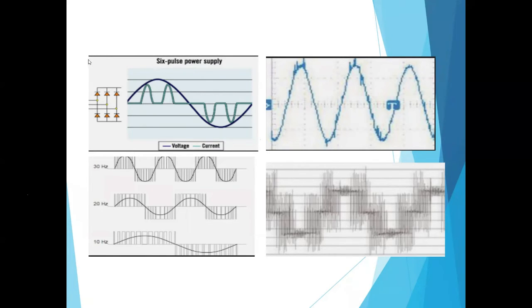There's also third, fifth, and seventh harmonic filters that will shave this off so that you don't feed it back. That's what the power company is worried about, is that noise on the input. Then on the output, if you run anything over 100 feet, you need to really start being concerned about it, from where the VFD inverter, which is the same thing, is to the motor, and if you have an older motor, to make sure that it has more spike resistant wire in it. There's also been a lot of things brought up about grounding rings inside the motor to make sure that you don't get circulating current. Part of that comes about from the tuning and the type of VFD that you have.